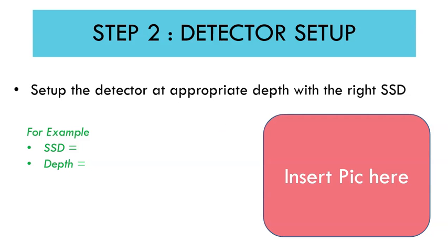Step number two is to set up the detector at the appropriate depth with appropriate SSD. This depends on the local site protocols, so follow that protocol.